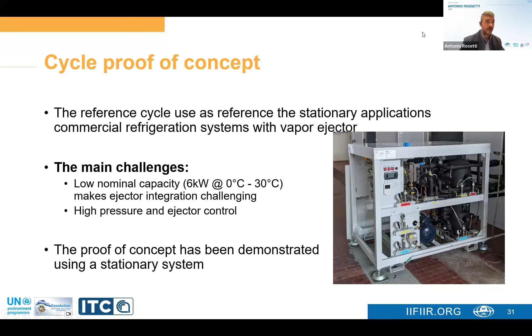So the ejector adds some complexity, but it's worth paying for because it can increase performance, both in COP and cooling capacity, for high ambient temperature, so for temperatures higher than 30 degrees Celsius.